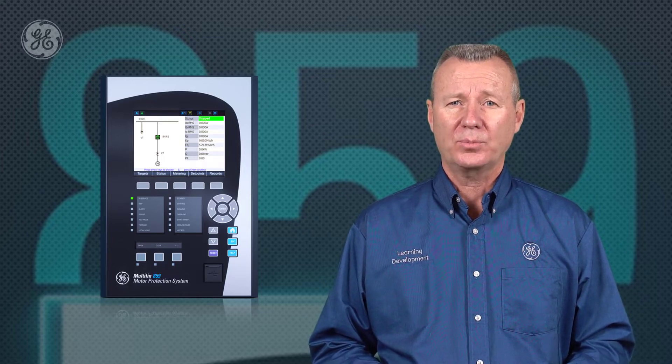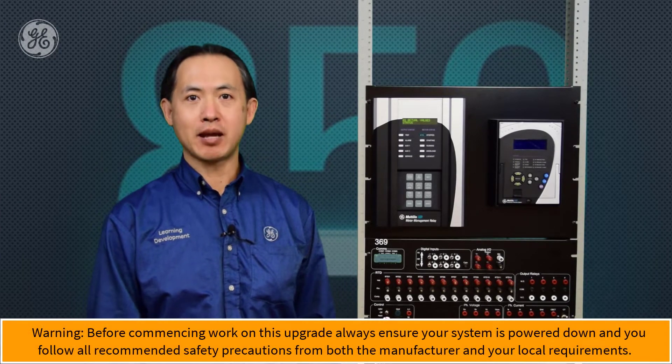Now that we've outlined how this upgrade is going to work, let's move over to our rack so our instructor can walk you through the process step by step. We have one 369 relay on the mounting rack, and we're going to replace it with one 859 relay. There will be three steps. The first is to do the settings file conversion from the 369 into the 859, which can be done automatically in the 8 Series EnerVista software.